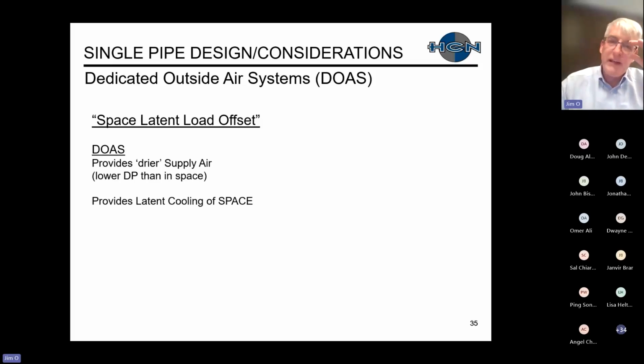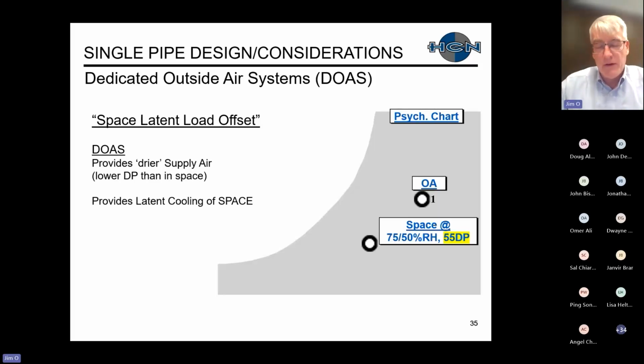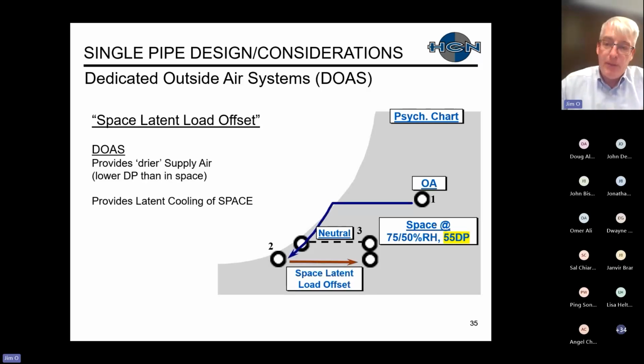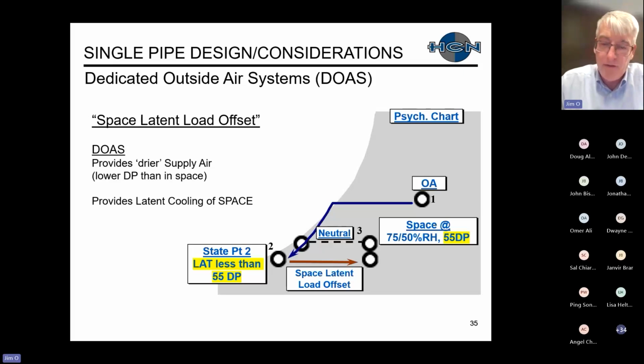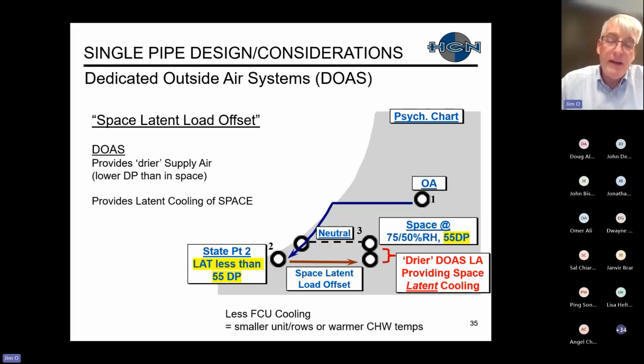Now let's talk about space latent load offset to help with the dehumidification in your zones. A DOAS unit in this case is traditionally providing neutral air to the space, where the dew point temperature of the leaving air from the unit is about the same as your space. What space latent load offset does is reduce the leaving air temperature from your DOAS unit to less than your 55-degree dew point in the space. That drier leaving air is going to help with the latent cooling in the space. And therefore, since we're helping the space, you'll require less cooling from the fan coil.